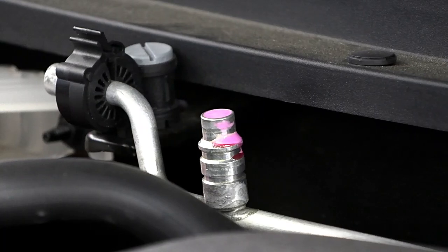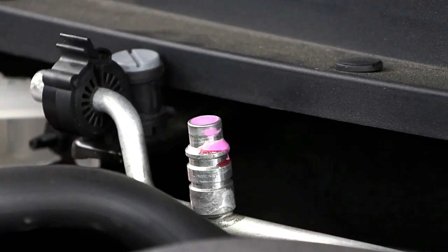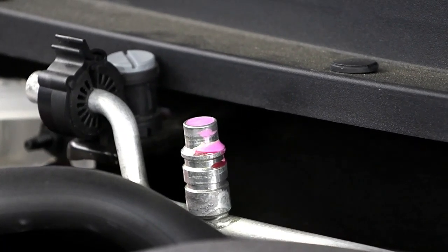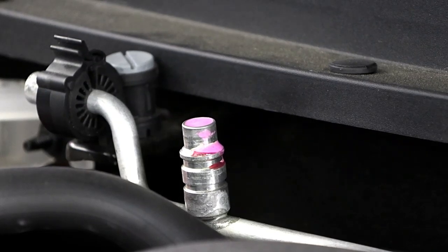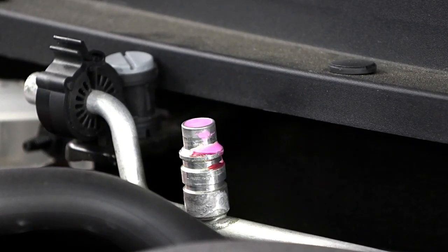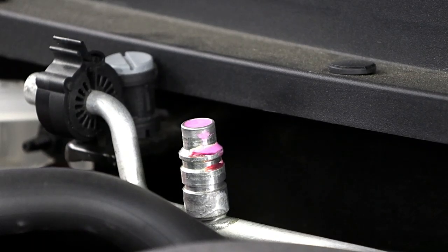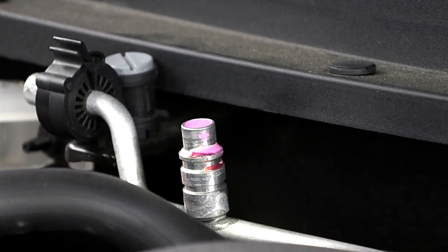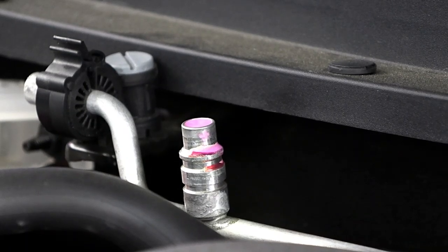Camera will adjust. There's some yellow up top, and there's a bubble in there, Bill? Maybe very slightly, so it has a small leak that the detector picked up. Yeah, it's bubbling, and it's starting to turn yellow. You can see the difference in color.